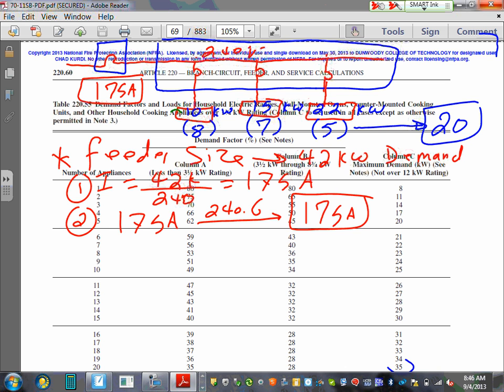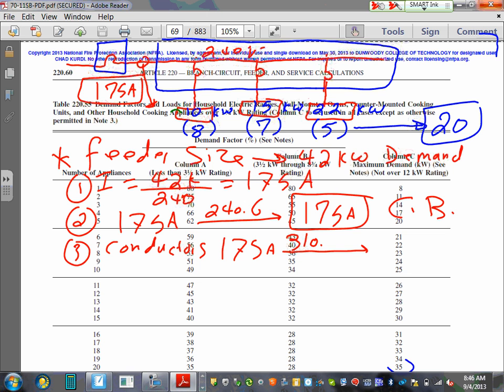Now we need to size the feeder, the wire here. We need to size it. So step 3: that was for the circuit breaker, now conductors. The same amps, guys, 175 amps. Take it to 310.15(B). Now we go to the special table, not, what was it, 15(B)(7)? Is it B7? Can somebody give me the name of that baby? Yeah, B7. Okay, what's the next size? 1 aught. So we're going to use 2 conductors, number 1 aught. 2 conductors, number 1 aught. Why 2 conductors?